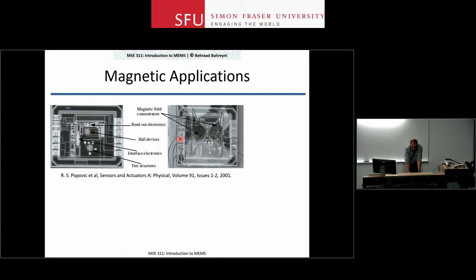So what they are doing here is that they have put some magnetic field concentrators. This is basically ferromagnetic material that they mixed with polymers and put right on top of the Hall effect sensor. What this does is that it acts like a lens. It focuses the magnetic field onto the Hall effect sensor, so you get a multiplication factor of, let's say, 5 or 10 or whatever, and then instead of a limit of half a Gauss for your sensor, you can maybe push it by another factor of 5 or 10.